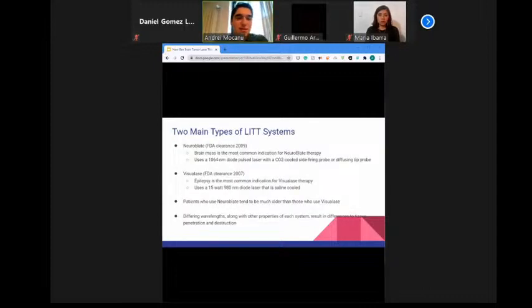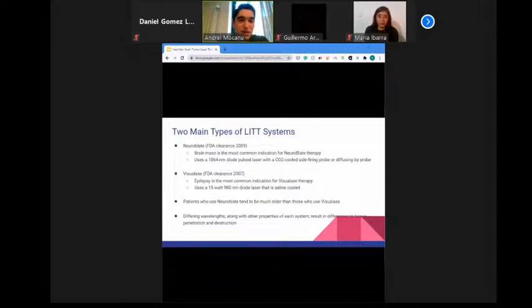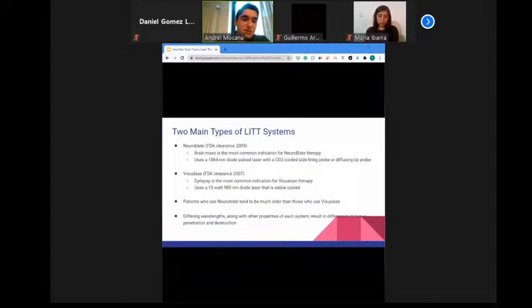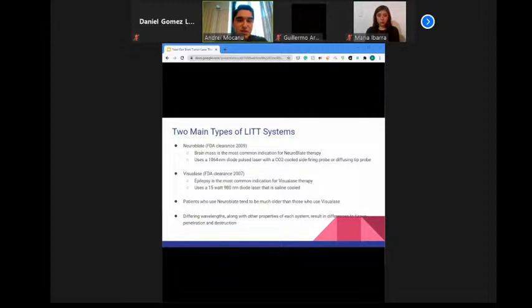There are currently two FDA-approved LITT systems: the Neuroblate system, which received FDA clearance in 2009 and is mainly used for brain tumors, using a 1064 nm diode pulsed laser with a CO2-cooled side-firing or diffusing tip probe; and the Visualase system, which received FDA clearance in 2007, is mostly used for epilepsy, and uses a 15-watt, 980 nm diode laser that is saline-cooled. Differing wavelengths and other properties result in differences in tissue penetration and destruction.